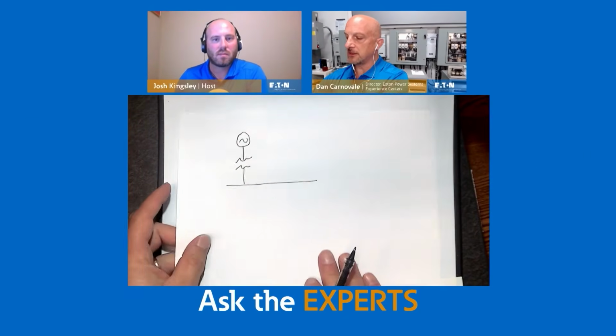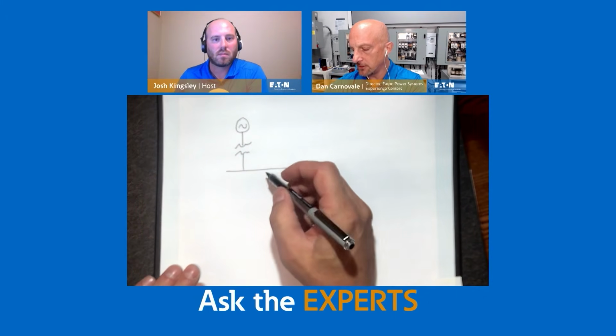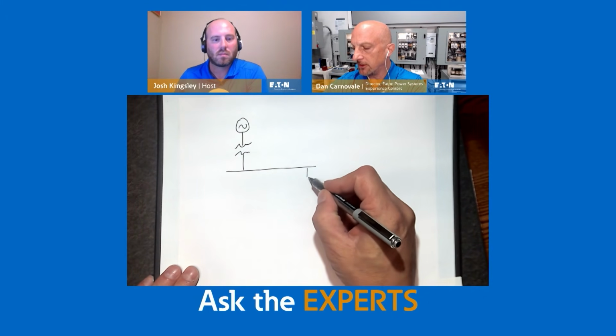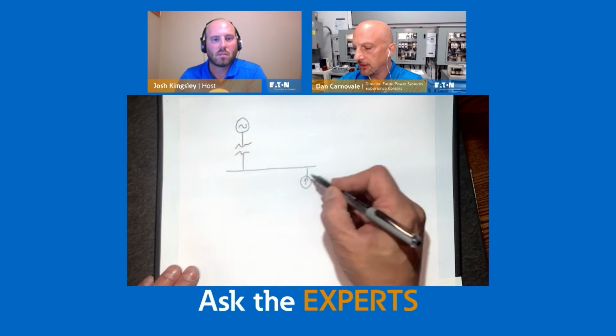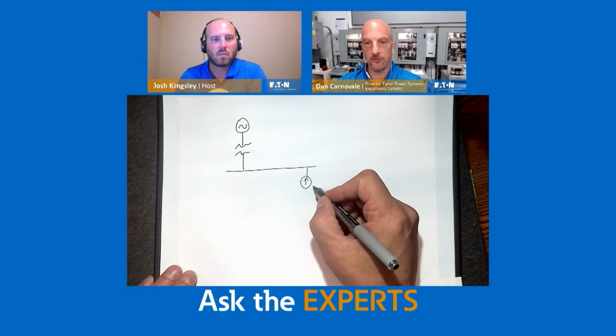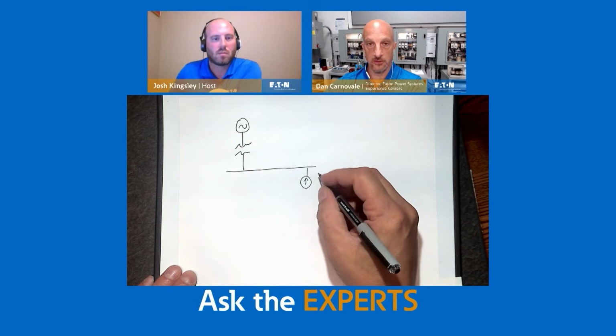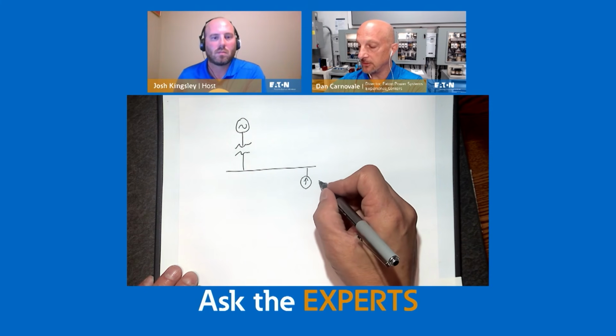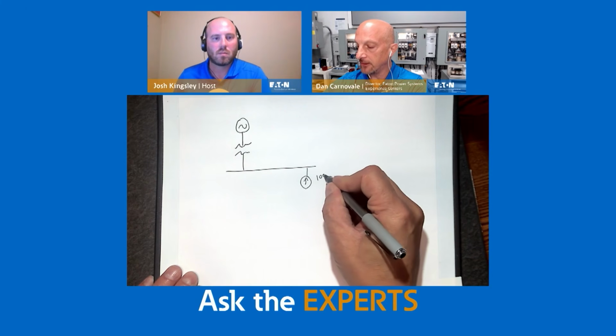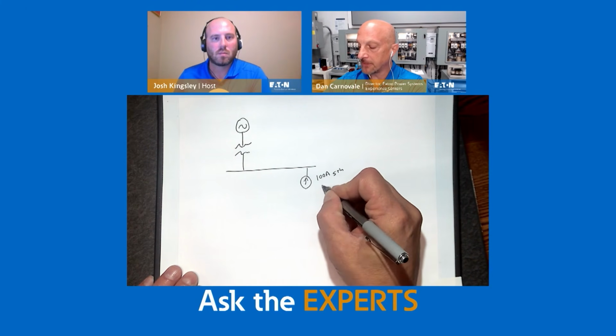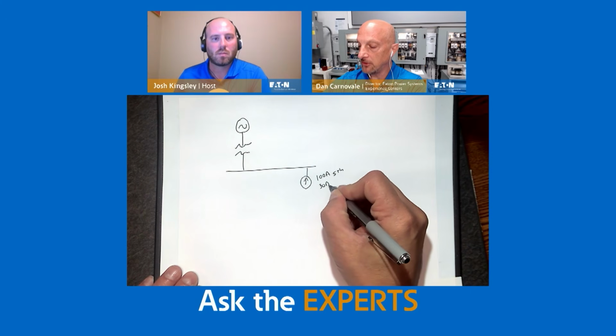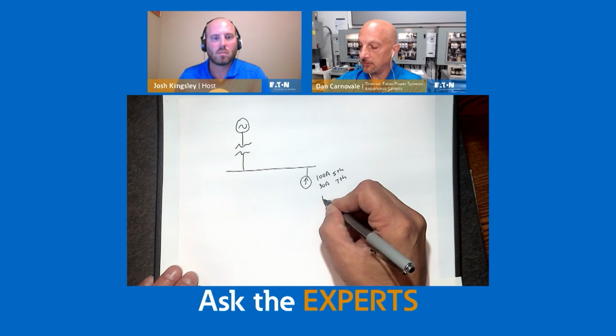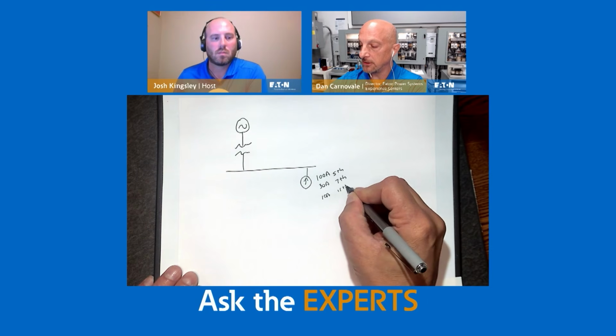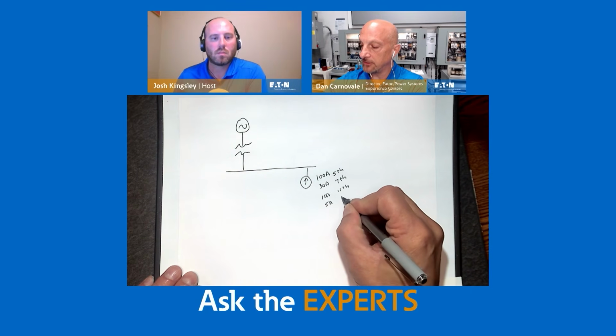Okay. I'm going to start over here with my drawing. And what I'll do is, let's talk about an active filter again first. So let's say you have, and I'm just going to draw it now in simplified form, just a constant current source. So no matter what your harmonic source is out here, we're going to say there's a certain amount of harmonics coming out of there. And that could be a combination of things. Let's say it's a 6 pulse drive. So maybe I have 100 amps of 5th harmonic current, 30 amps of 7th harmonic current, 10 amps of 11th harmonic current, and 5 amps, as an example, of 13th harmonic current.